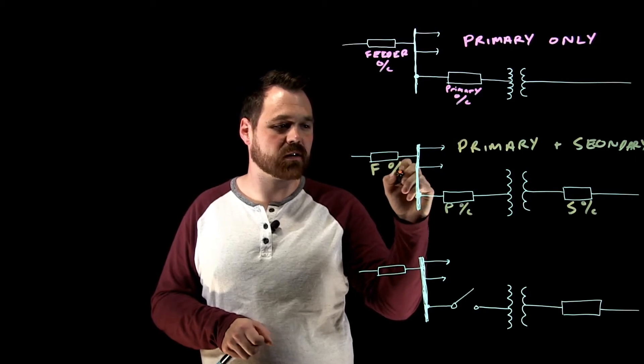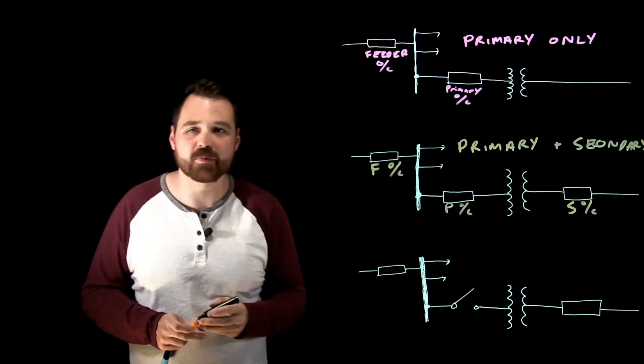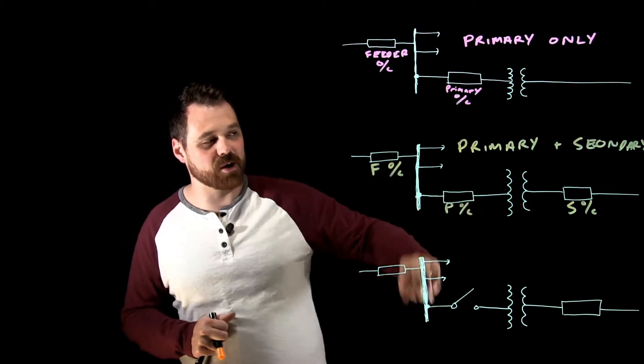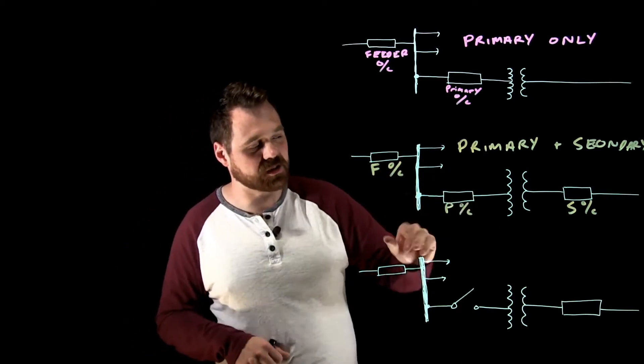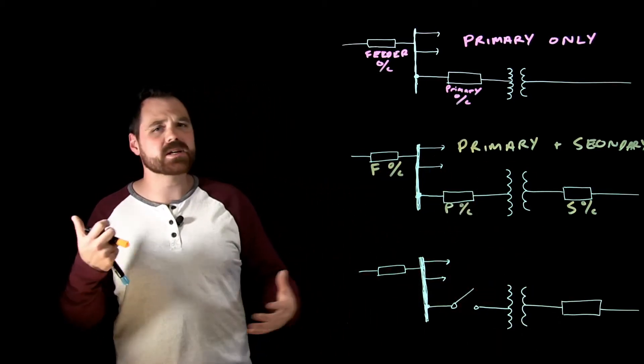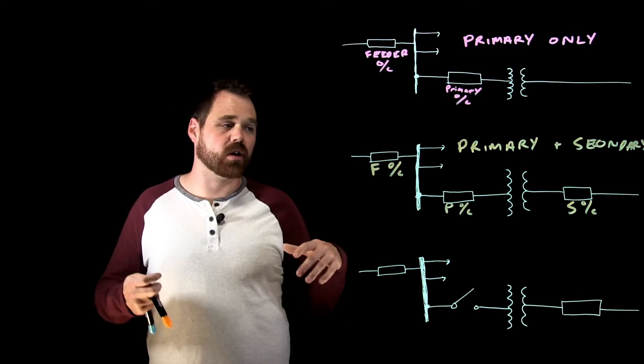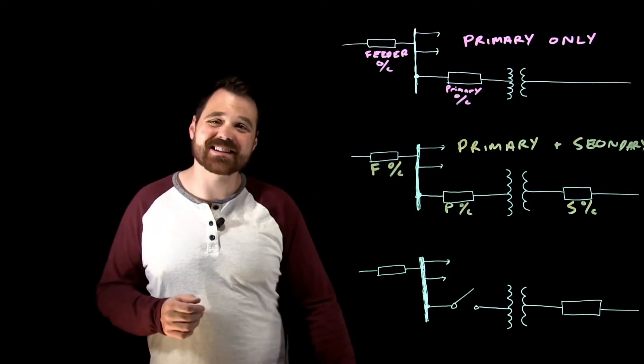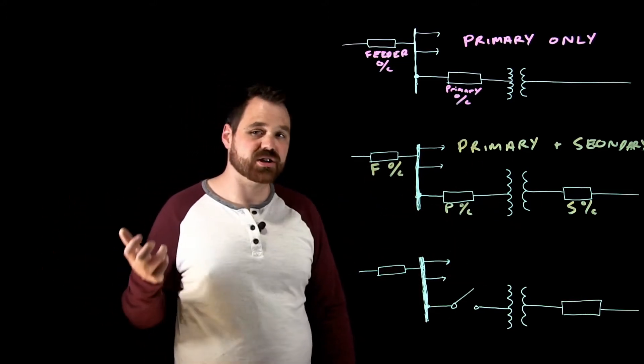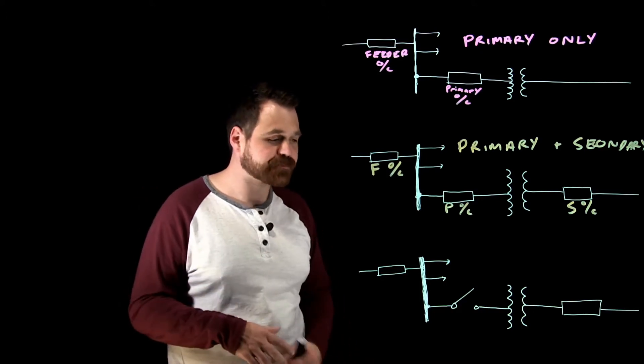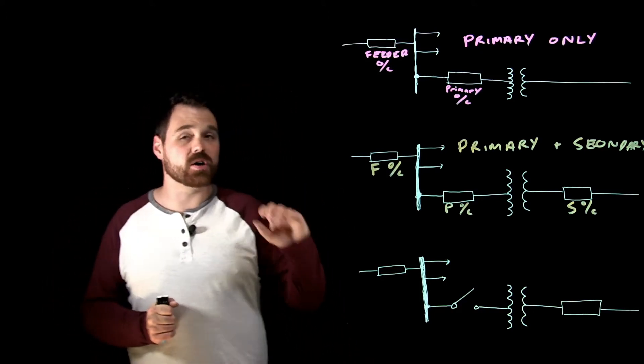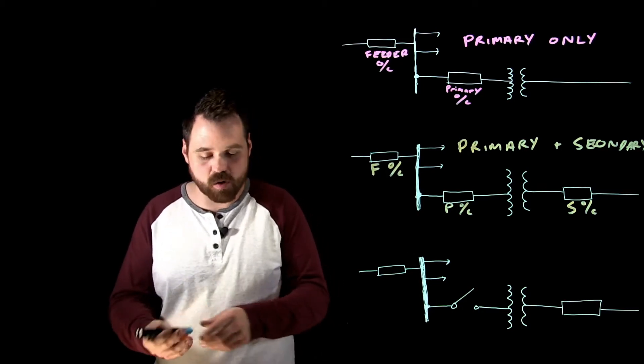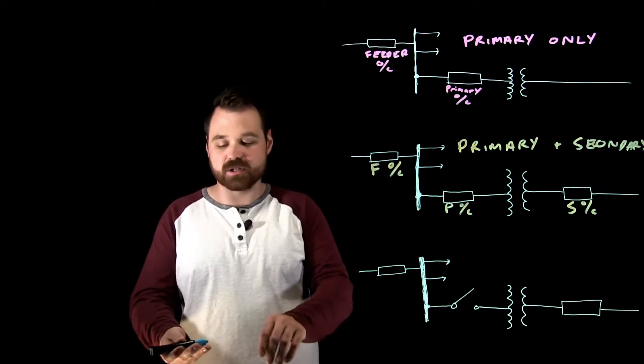I also have my feeder overcurrent protection over here. This one's a little bit overkill because, as we discussed, the primary will protect the primary and the secondary. But some specs for different jobs or certain applications may require that secondary overcurrent protection as well. The middle option is not too common, but the code book does give us the requirements in order to size that.